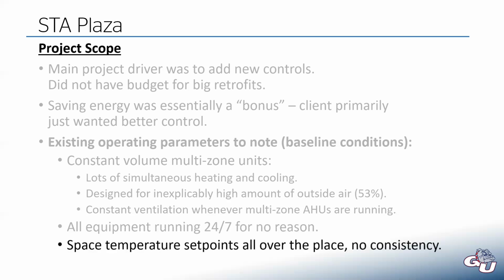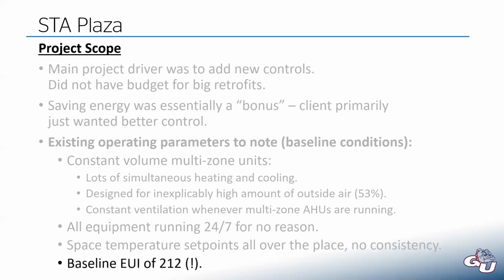Their space temperature set points, so the temperatures at which they're maintaining within the building, were all over the place. So there was no consistency at all. And in some cases, you could have some pieces of equipment in one area of the building with much higher or lower set points than in adjacent space, and you could end up with those spaces fighting each other because no zone is truly in isolation. There's always some communication and transfer of heating energy within that building. So the baseline EUI was 212, which is massive. That is extremely high.